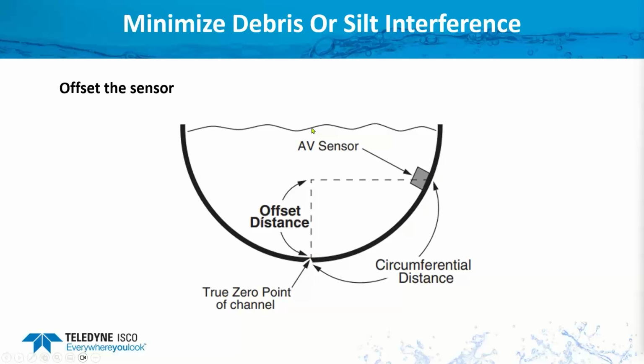But just a note on this, in this example here, if I had the sensor at the bottom and this is my water depth and it was 6 inches, I would calibrate my sensor to 6 inches. If I rotate it up off the side, my water depth is still 6 inches, so you'd calibrate your level to 6 inches. But the other thing is, depending on the equipment, you could tell it that you have it offset, so that when, in this case, the level gets lower than 4 inches, it stops reading velocity because it's out of water.